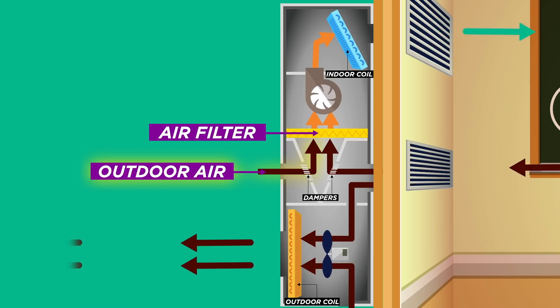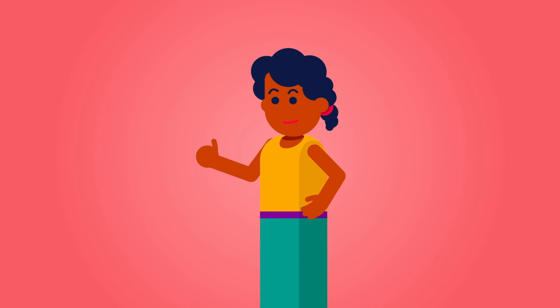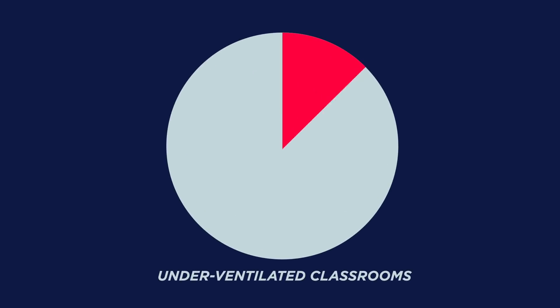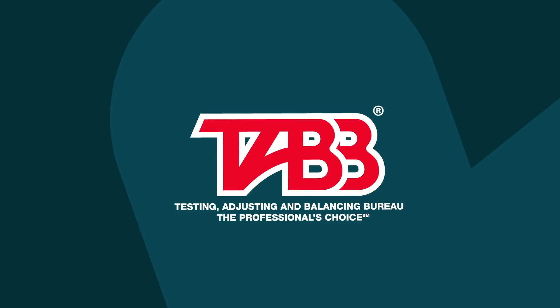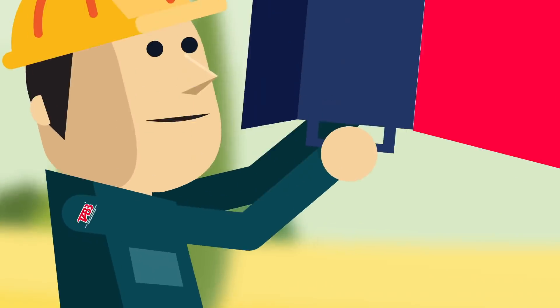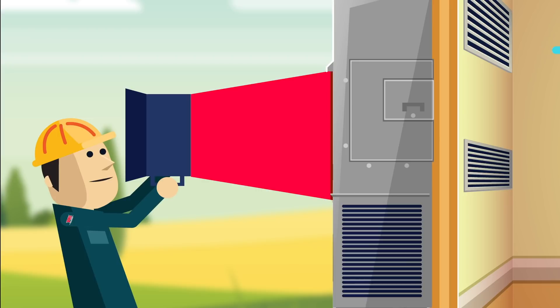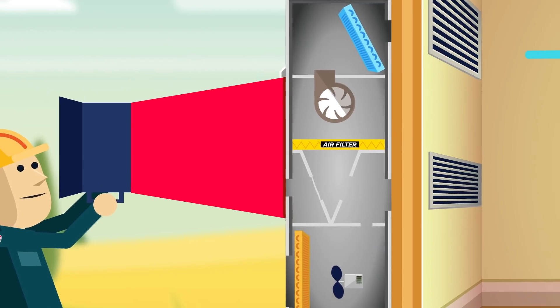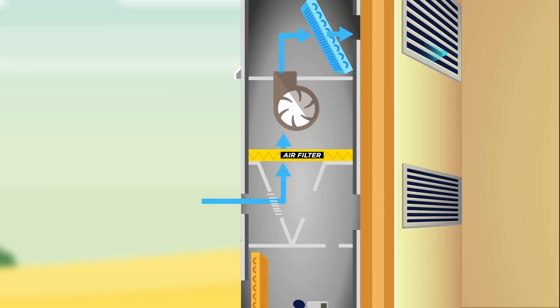How do you know if a classroom is getting enough ventilation? You may think that teachers can detect a problem, but most cannot. In a recent study where teacher surveys were compared to ventilation rates, over 60% of teachers in underventilated classrooms reported that their satisfaction with their indoor air quality was neutral or satisfied. In order to know if a classroom is well ventilated, the HVAC system's ventilation rate must be measured and, if necessary, adjusted to meet the classroom requirement. This should be done by trained, qualified, and certified personnel.